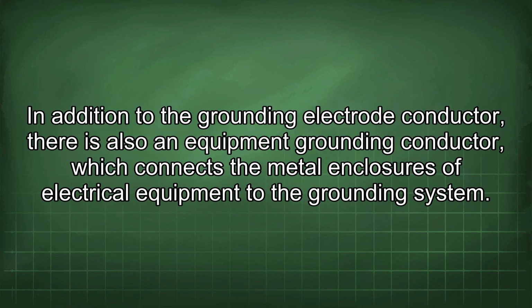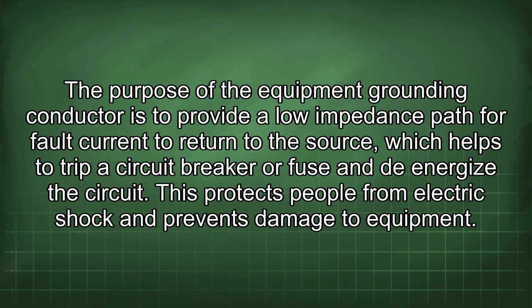In addition to the grounding electrode conductor, there is also an equipment grounding conductor which connects the metal enclosures of electrical equipment to the grounding system. The purpose of the equipment grounding conductor is to provide a low impedance path for fault current to return to the source, which helps to trip a circuit breaker or fuse and de-energize the circuit. This protects people from electric shock and prevents damage to equipment.